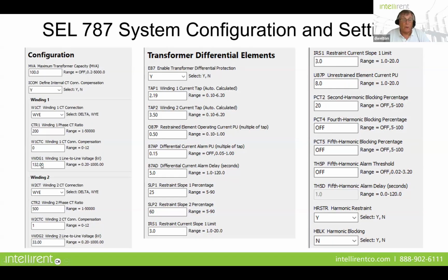Okay, and then the voltage level, and then we go to winding 2, which is Y connected. It's got a compensation of 1, which actually equates to 30 degrees, a CT ratio of 500, and the secondary winding voltages as well. So we will say that we enabled this element. And the thing about the Schweitzer is once you put this information in, your tap settings will automatically be configured. And that's the big difference between the two.